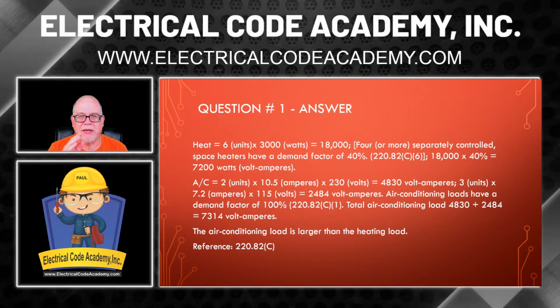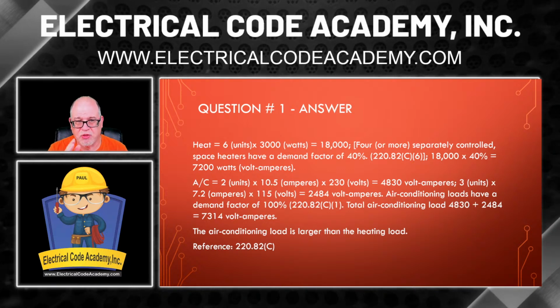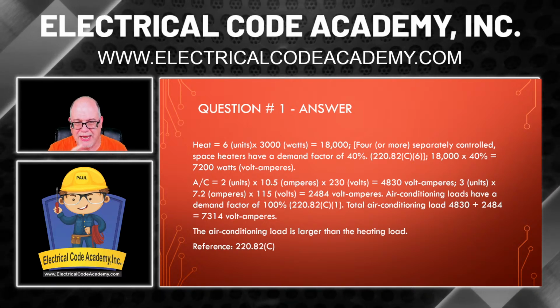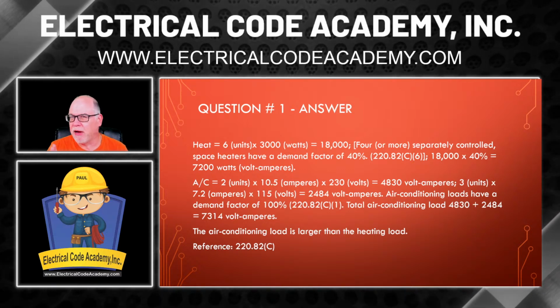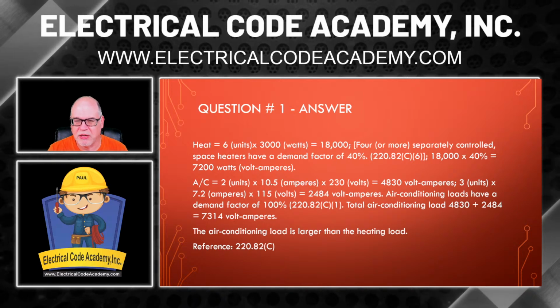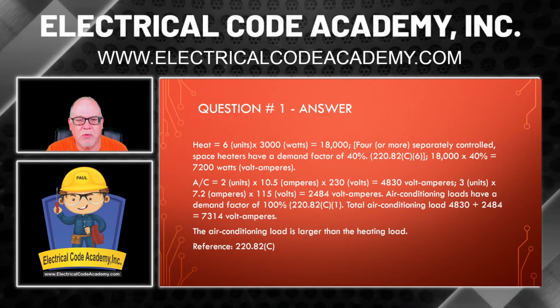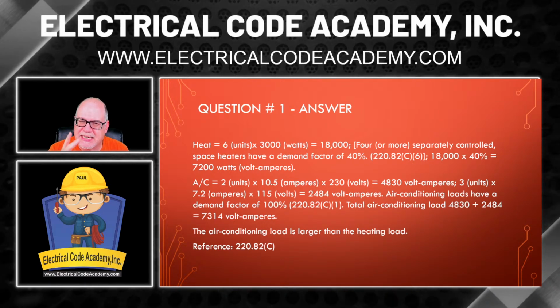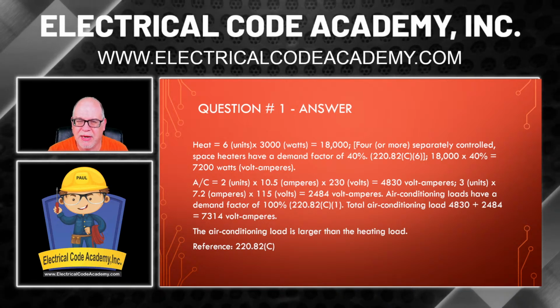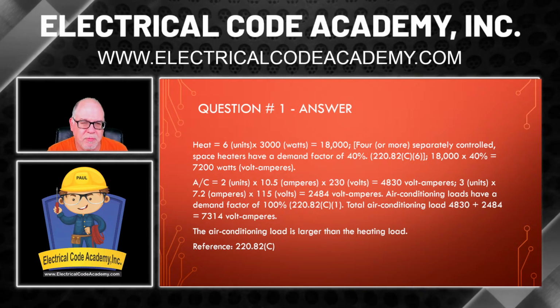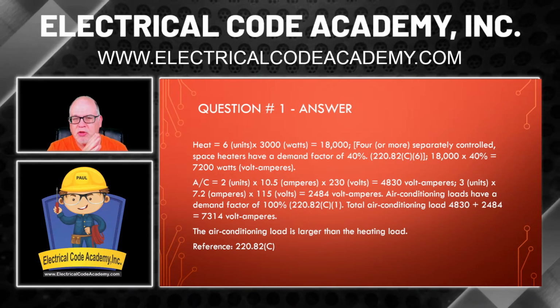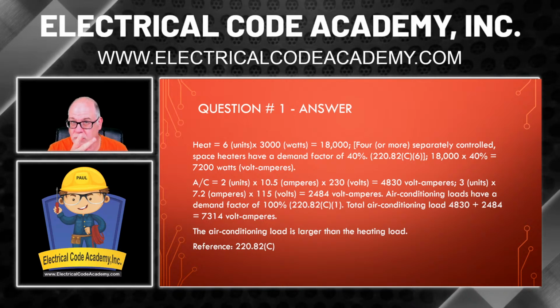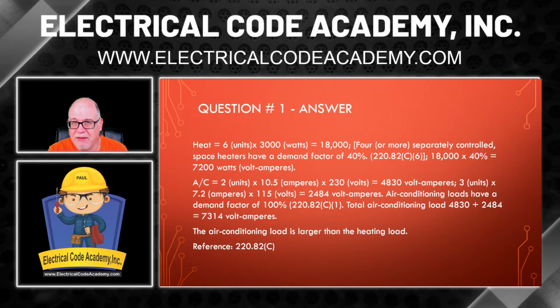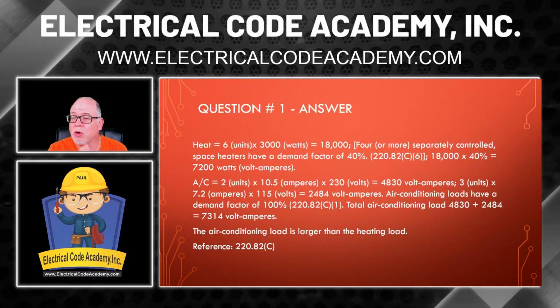Now let's look at that AC, because we know that we've done the heat already, and 7,200 is what we're working with for the heat. Is that going to be greater than the AC? Well, that's what you've got to work out. Remember we had 2 of them at 10.5 amps each, and we had 3 of them at 7.2 amps. So easy math: 2, because there's 2 of them, times 10.5 times 230 volts.